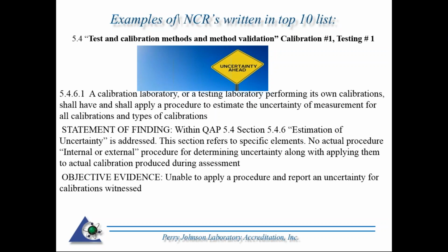So an example of a finding, and actually I've changed some names to protect the innocent on here. I've captured some things on some assessments that I've personally been on. So this particular one states within a QAP, Quality Assurance Procedure, Section 5.4.6, Estimation of Uncertainty is addressed. This section refers to specific elements, but no actual internal or external procedure for determining uncertainty along with applying them to calibrations produced during an assessment.